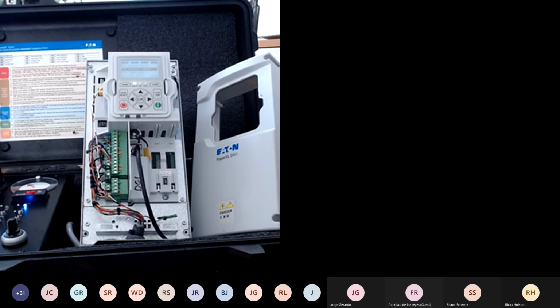But as long as you have a 230 volt single to three-phase, you can actually have some great solutions if that is all you have in your system, without having to redo your single line diagram. And obviously the input protections, the UL rating, the NEMA rating is all according to that. The caveat is you cannot have a bypass when you have single to three-phase applications, because the VFD is what's using that single phase and replicating that into a three-phase going back onto your machine. Again, when you are going through single to three-phase applications, there's a specific oversizing and potential capacitors that you may need to use to be able to have the application work. So that is if you're using that in the field.